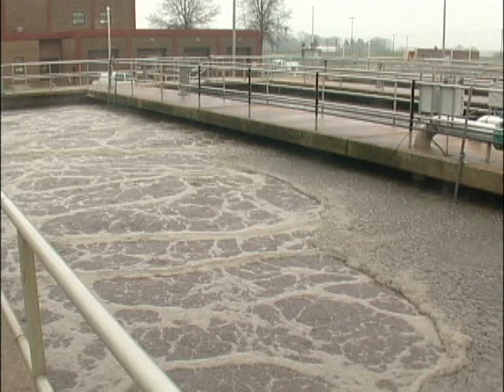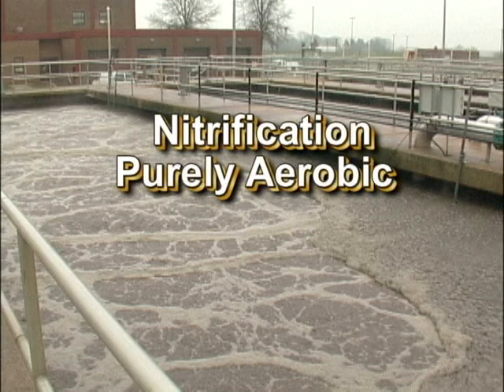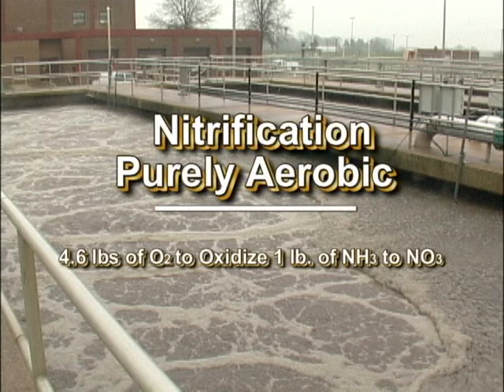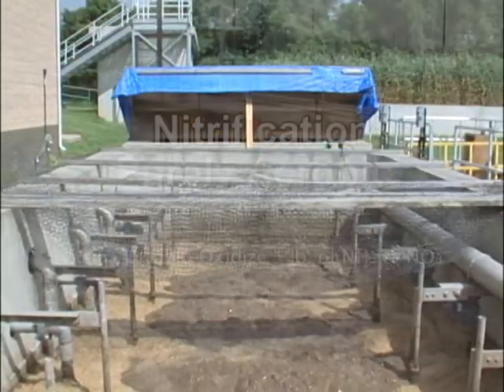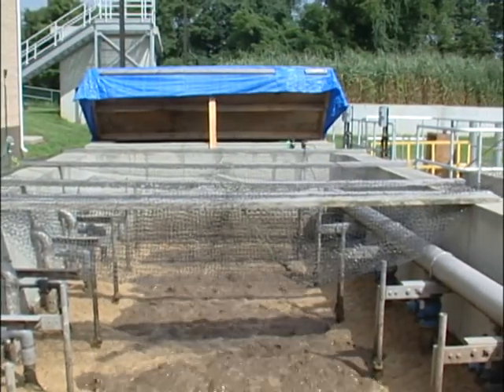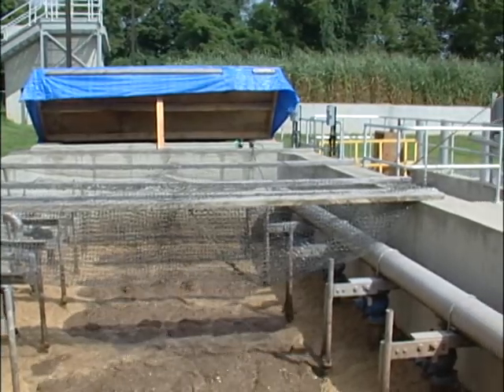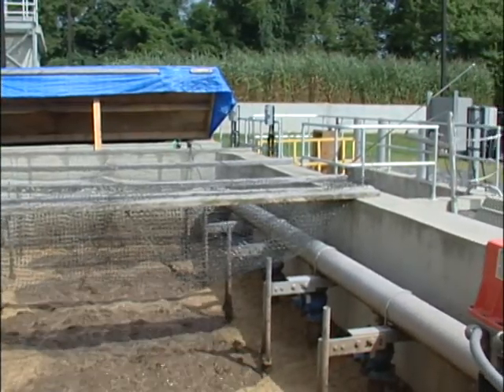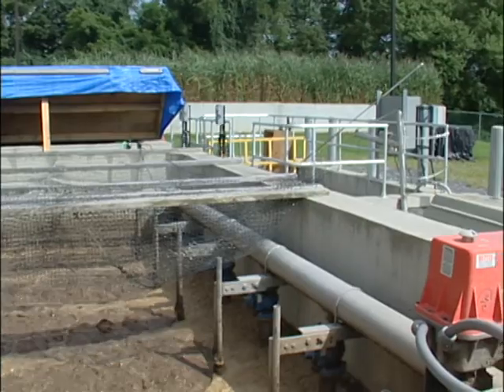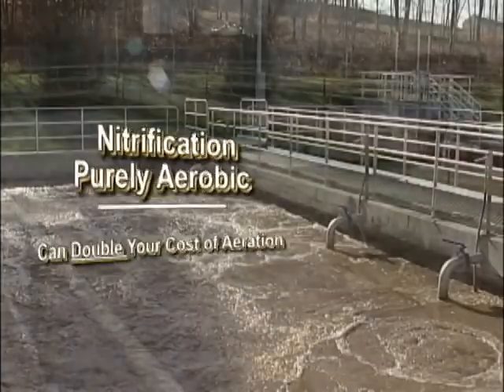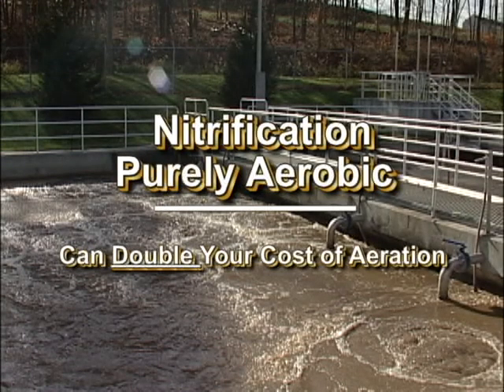Nitrification is a purely aerobic process that requires a large amount of oxygen. In fact, it requires 4.6 pounds of oxygen to oxidize 1 pound of ammonia into nitrate. Comparatively, it takes approximately 1.1 pounds of oxygen to oxidize a pound of BOD. The requirement to nitrify can almost double your oxygen requirements and aeration costs.